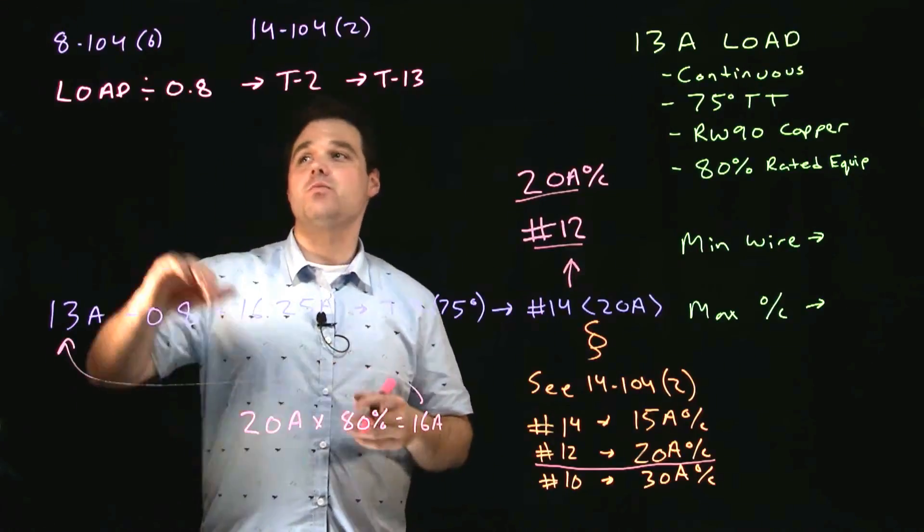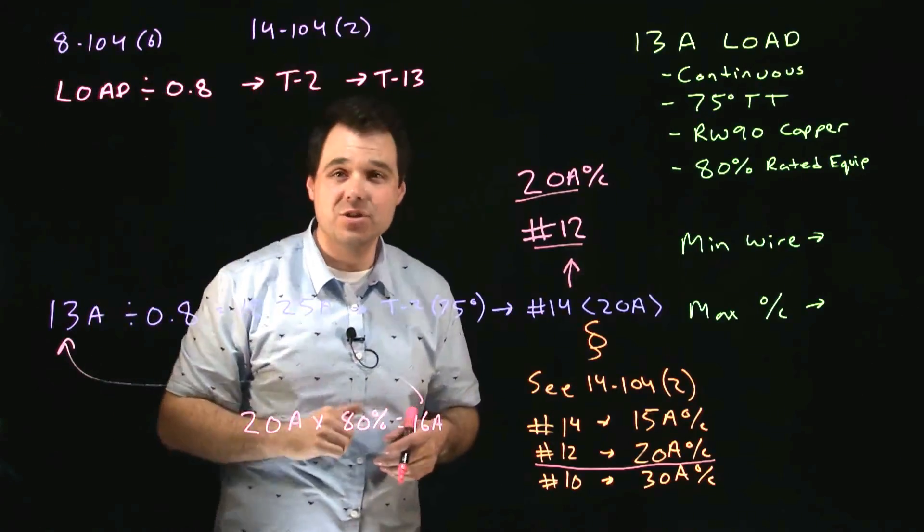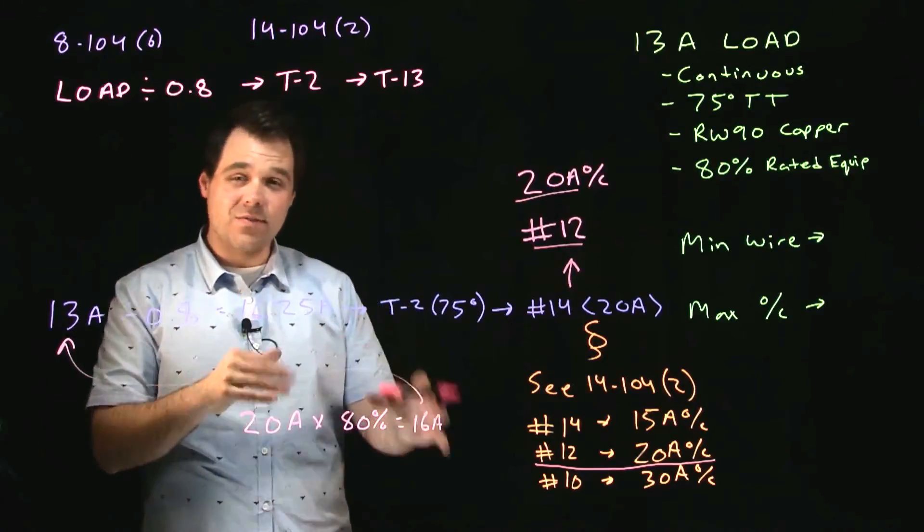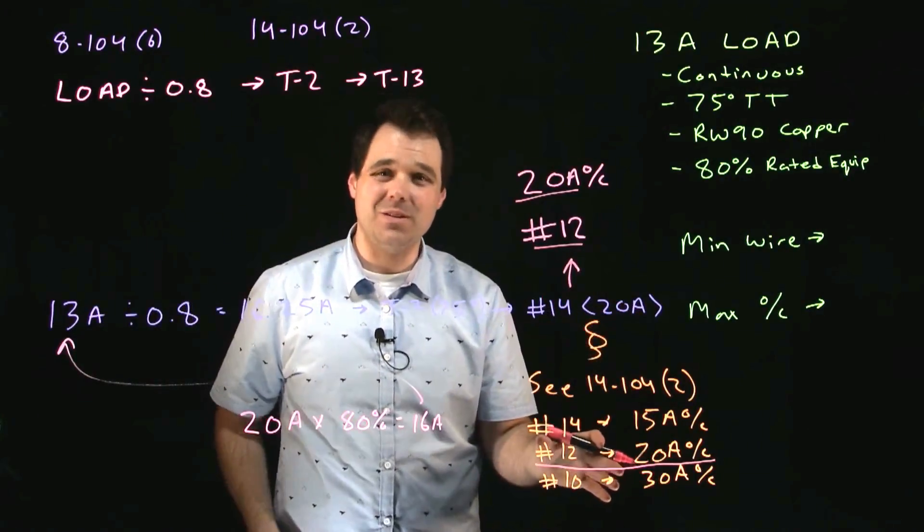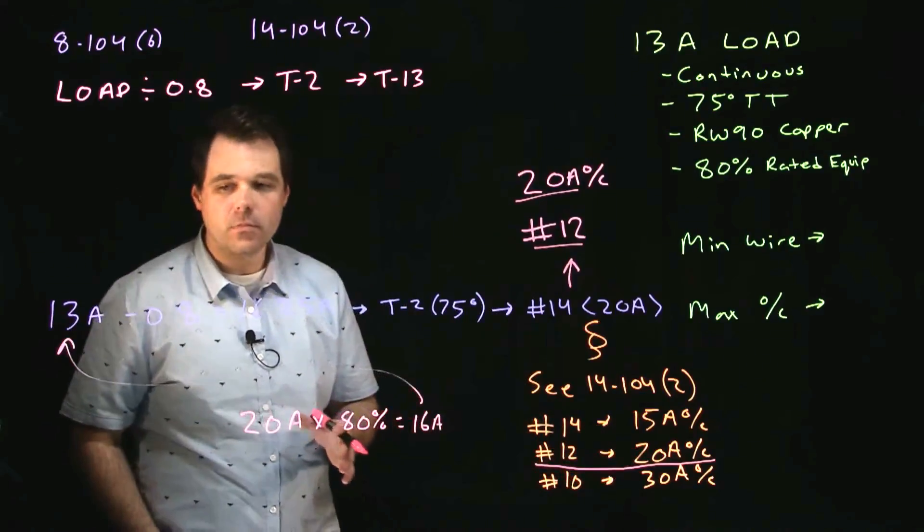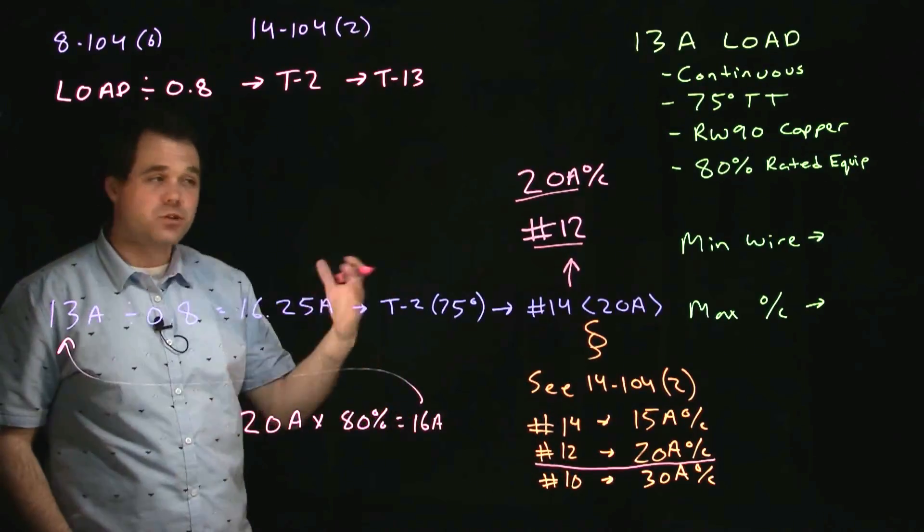So kind of two little tricks with this one. We did a continuous loading calculation like we normally would. Only at the very end we had the double squiggles. We have to pay attention to 14-104 sub rule 2. So two different steps there. Two different processes.